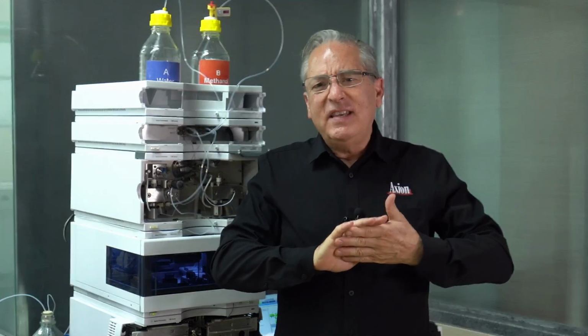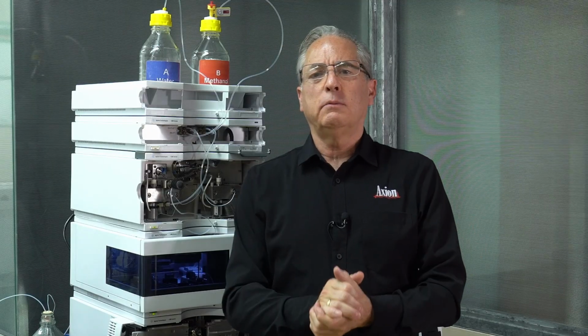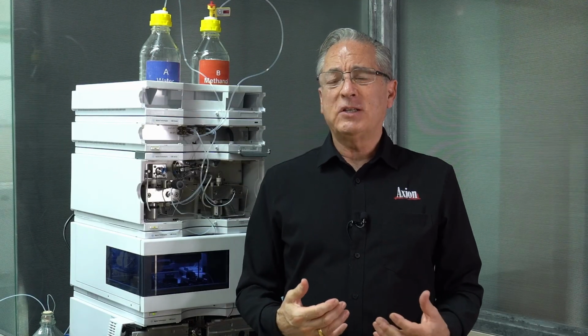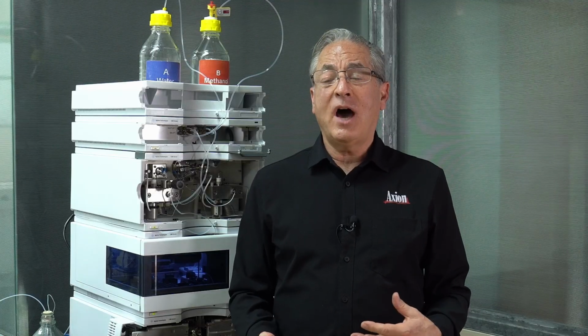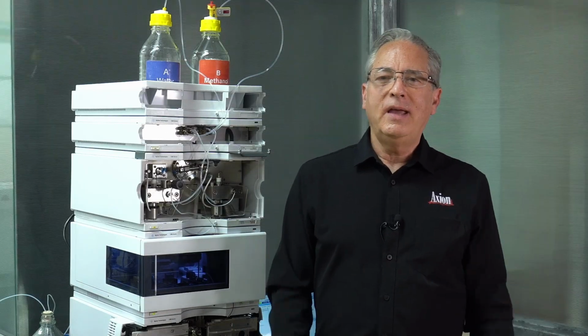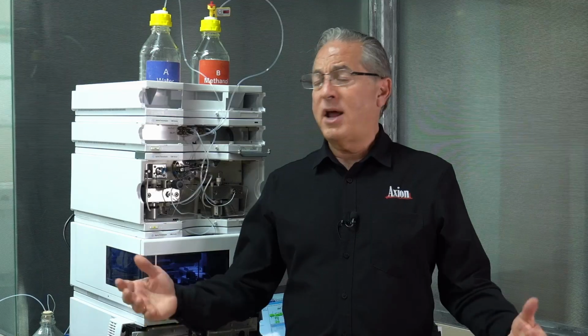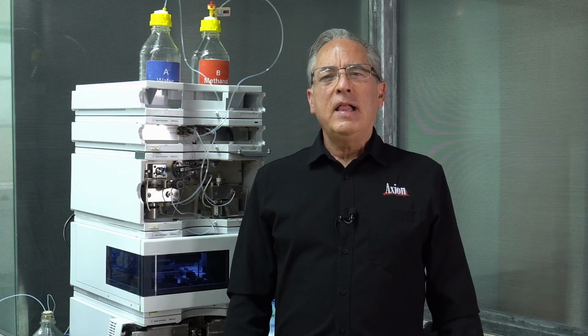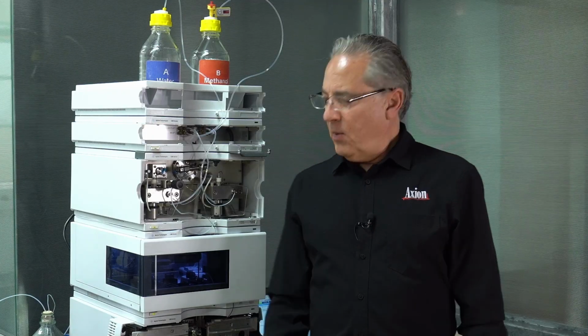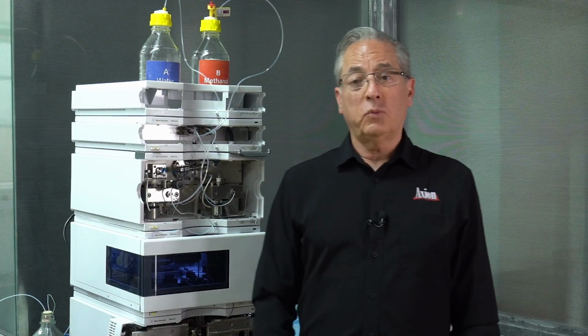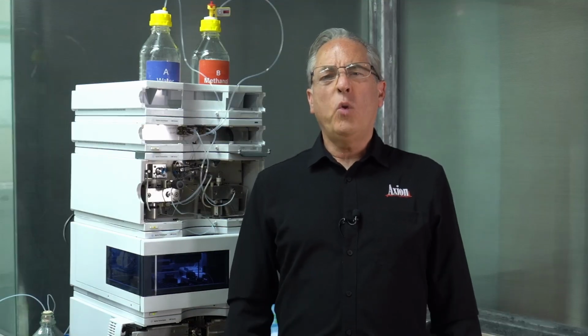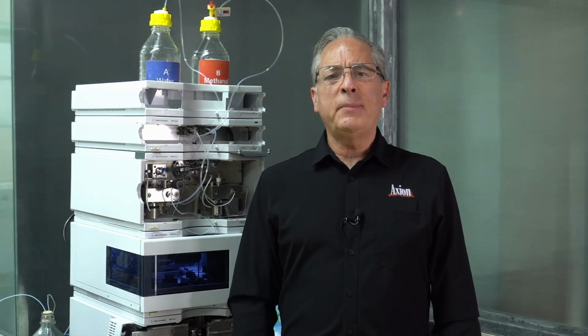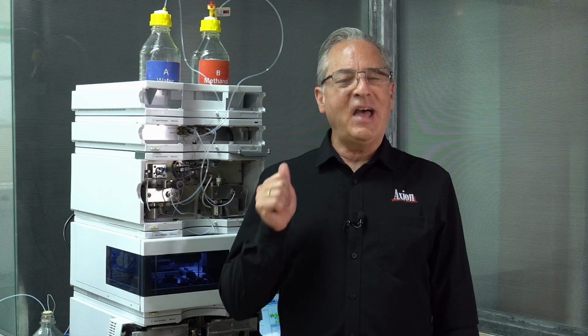The next piece of the LC that needs maintenance, we'll talk a little bit about maintenance of the autosampler. So the first question I always ask is, how do I know my instrument's broken? Instead of saying, let's just go in on a random Thursday and start taking things apart, let's decide when something's broken, when it needs to be fixed. So how do I know my autosampler has a problem? Well, let's turn the question around. What's the autosampler's job? Its job is to inject the exact same amount of sample every single time.